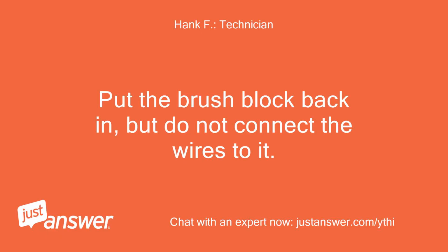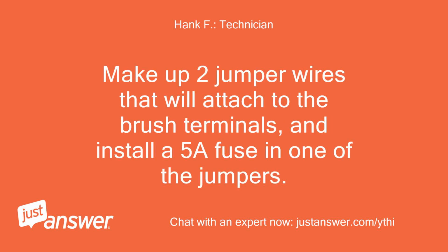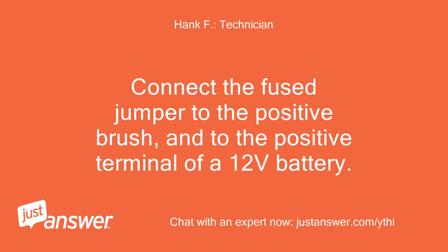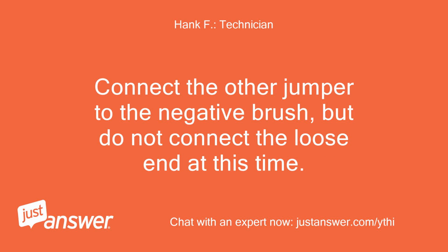Put the brush block back in, but do not connect the wires to it. Make up 2 jumper wires that will attach to the brush terminals, and install a 5A fuse in one of the jumpers. Connect the fuse jumper to the positive brush and to the positive terminal of a 12 volt battery. Connect the other jumper to the negative brush, but do not connect the loose end at this time.